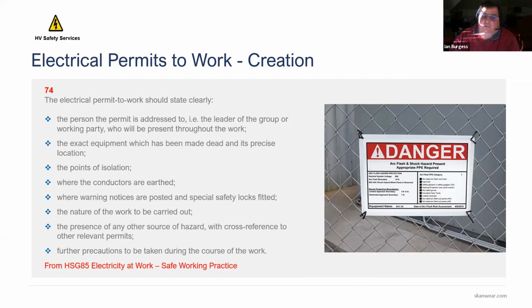So, creation of permits. What should they say? It should say who the permit's addressed to, the leader of the working party, the exact equipment that has been made dead, and the precise location of where that equipment is, where the points of isolation are, where conductors are earthed if they're applied, where warning notices are posted and safety locks fitted, what the work is that's to be carried out, the presence of any other source of hazard, and cross-reference to other permits if applicable, and anything else that might need to be taken on site, such as putting earths down for induced voltage, for instance.